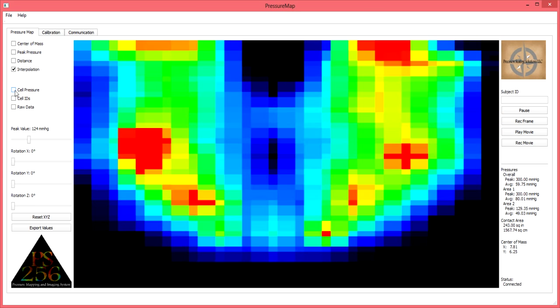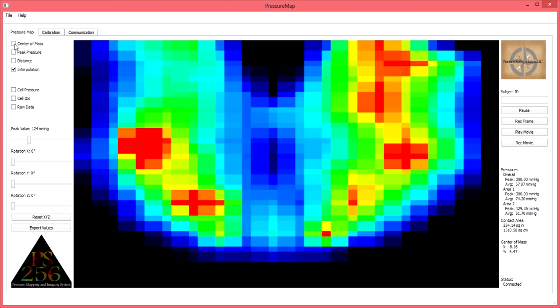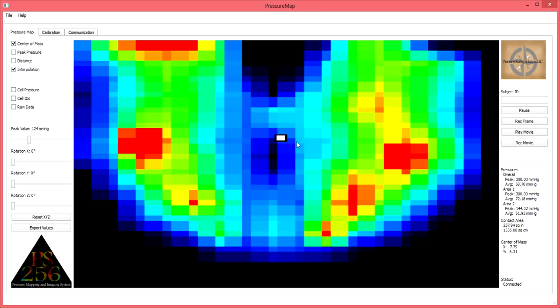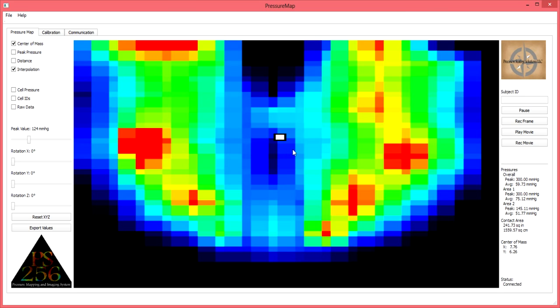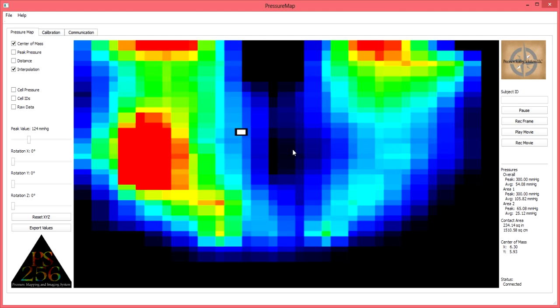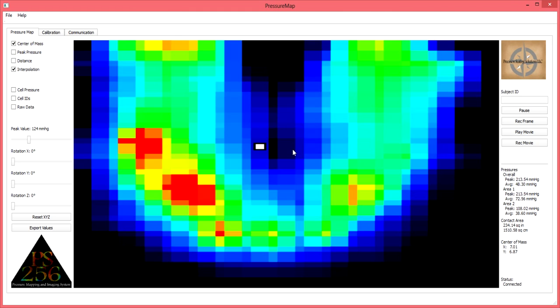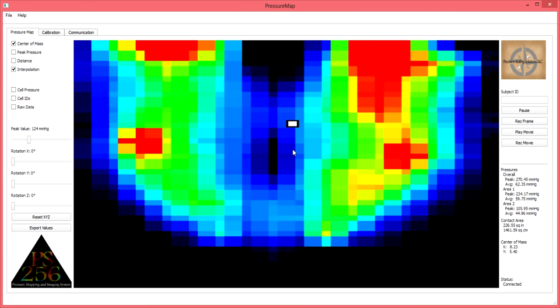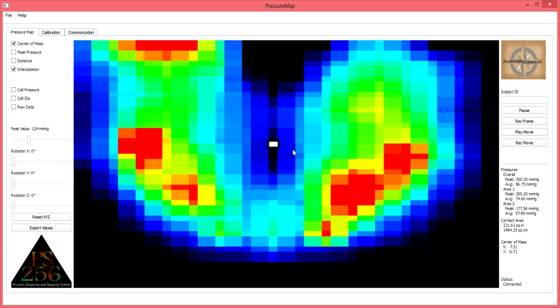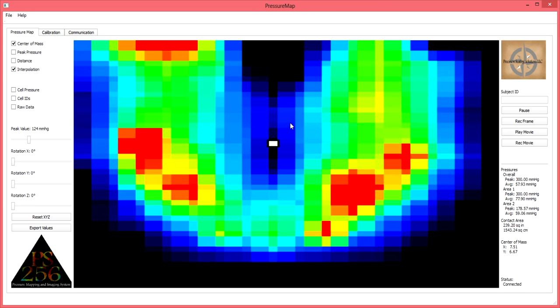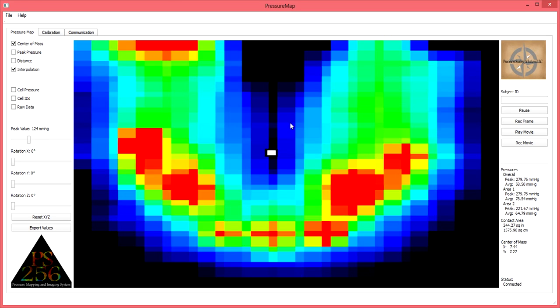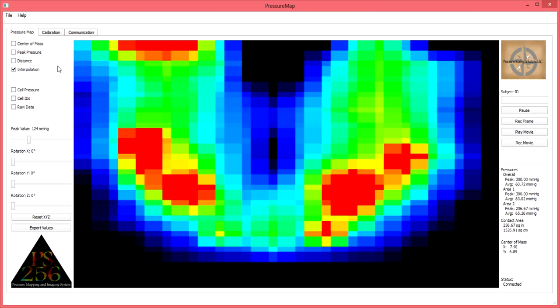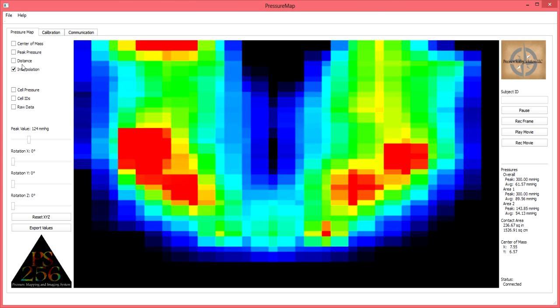Above the peak pressure selection tool, on the upper left hand side of the screen, is the center of mass selection tool. When selected, you will see a small white box with a black outline pop up on the display screen. This white indicator identifies, on a continually updating basis, the location of the client's center of mass. A variety of uses for this feature are discussed in our clinical application tutorial, including several ideas for implementing the PS256 into a billable treatment plan. To turn this center of mass feature off, deselect the box next to this tool.